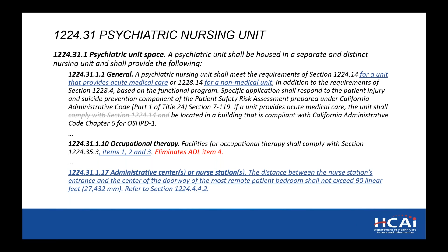For occupational therapy, we're eliminating the activities of daily living requirement, item 4. So we're just saying you must comply with 1224.35 for rehab for items 1, 2, and 3. This is for occupational therapy. The activities of daily living is primarily for people that have amputations or some medical condition where they're learning to restructure their lives and live at home independently. In a psych unit, that isn't really required, so that has been eliminated. And again, another alignment with Title 22 is the requirement that in a psych unit, the beds shall not exceed 90 linear feet from the nurse stations. That fell out of the code years ago, and that should have never been removed. And again, that's because of a safety factor with observing patients.